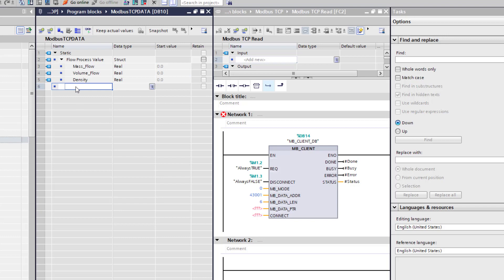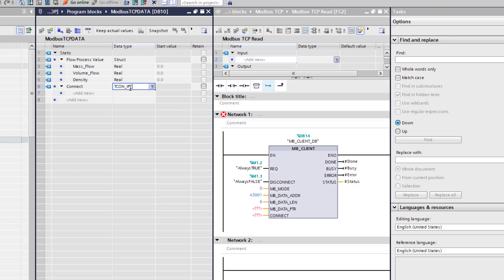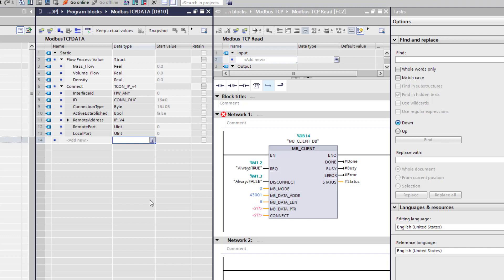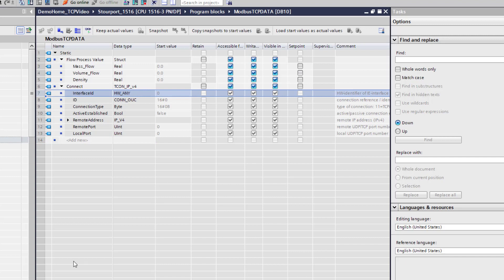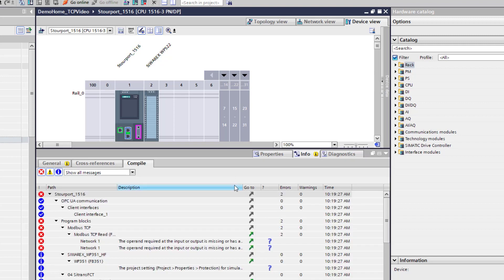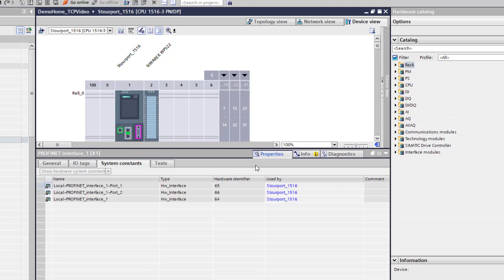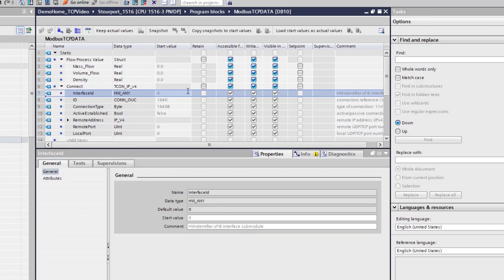We are starting a new data structure. And this is a standard data structure within TIA portal. We will call it connect. That is its name. And then under here if you type in TCON underscore IP underscore V4 and just hit enter, you will see an array of information come up now. So we need to fill some of this in. The first one is the hardware interface. So if we go to the S71500 PLC, we are connected on this port physically. So if we go to properties, system constants, and then it is this local interface here. So 64 is my hardware identifier. So we will put that in.